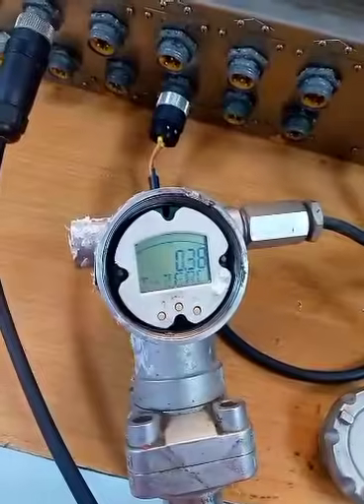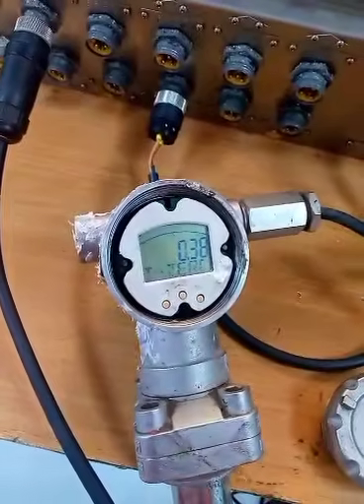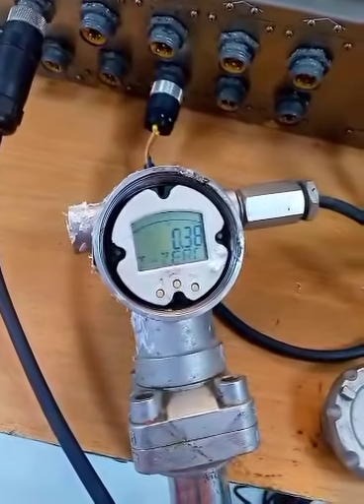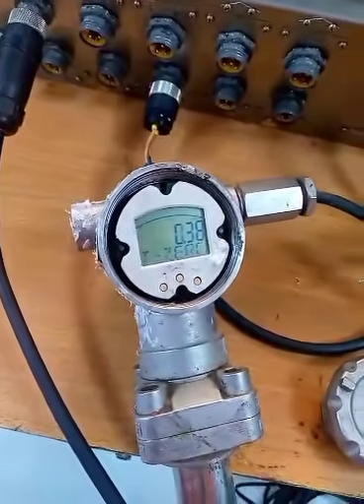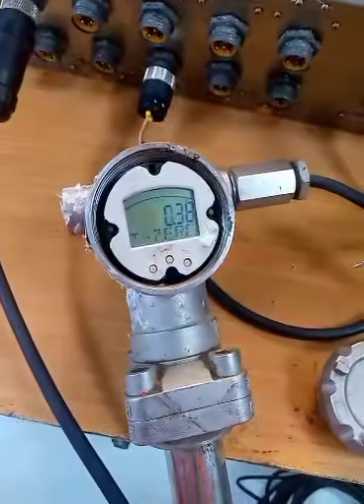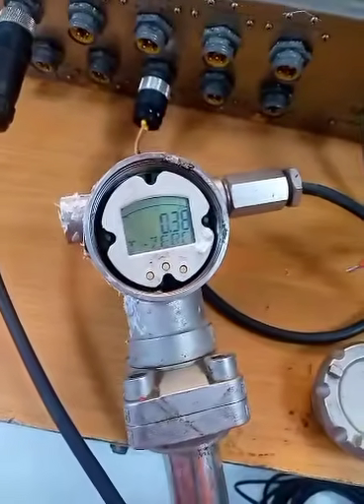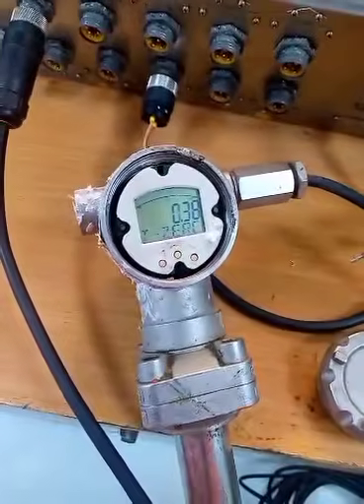So with that 4 milliamps, you calibrate it with reference to the air density, which I said is 0.0102 ppg. That means you have taken care of your low calibration.